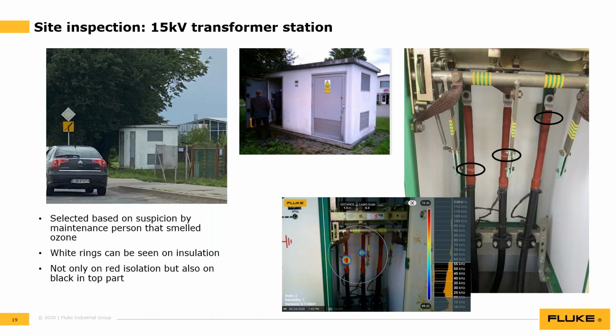Another common place to find partial discharge would be something like this on a transformer station and on the bus bars. This picture on the right shows that you could visually see there might be an issue if you look closely, because there's some tracking on the outside. But the view of the acoustic imager quickly and precisely locates where that's coming from.